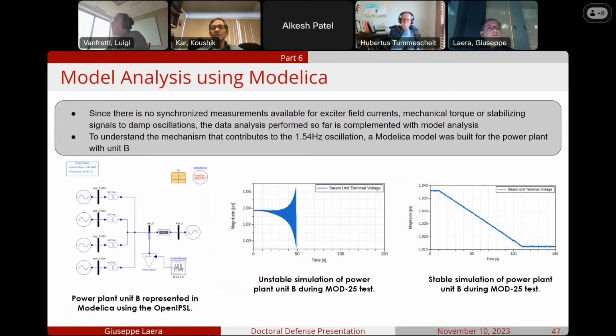But since there are no synchronized measurements available for exciter field currents, mechanical torque, or stabilizing signals to damp oscillations, models are necessary to complement the data analysis performed so far. And the Modelica models for power systems can be built using OpenIPSL, exported as FMUs, and simulated in the cloud, the same environment where real data is analyzed via dedicated Python libraries. In order to proceed with the analysis and understand the mechanism that contributes to the oscillation, the Modelica model was built for the power plant unit B substation, as we can see down here.